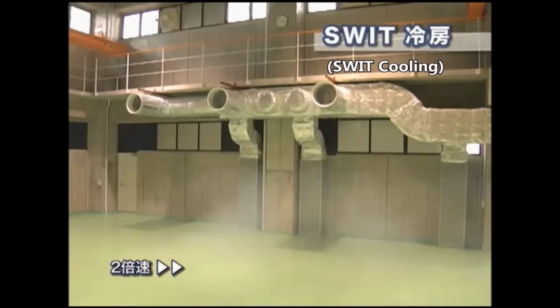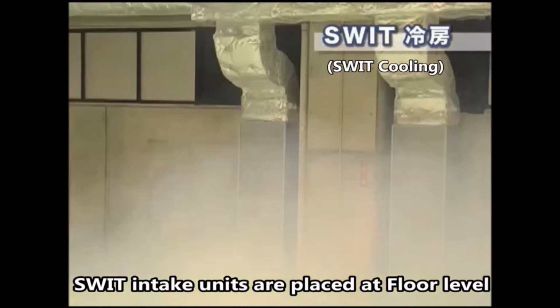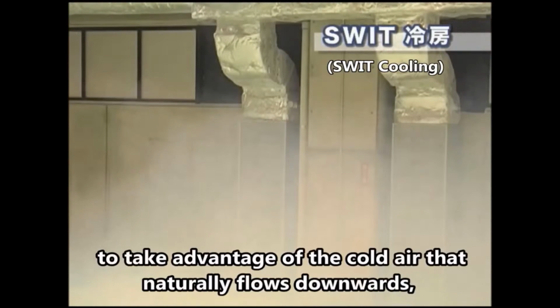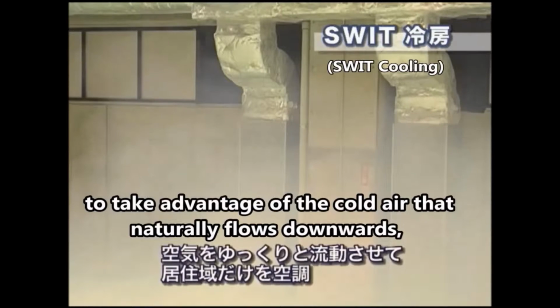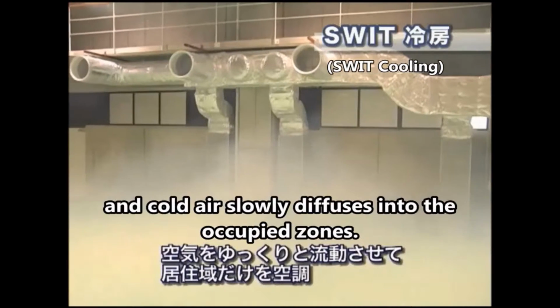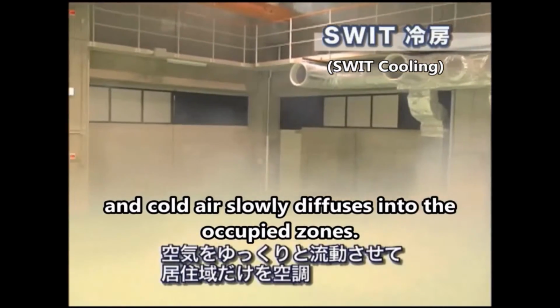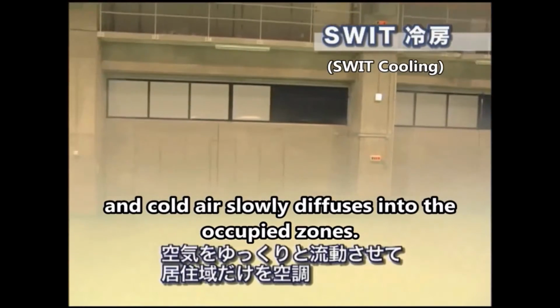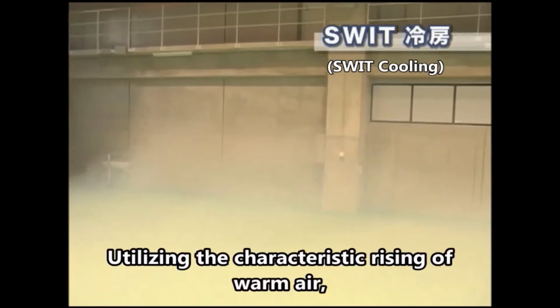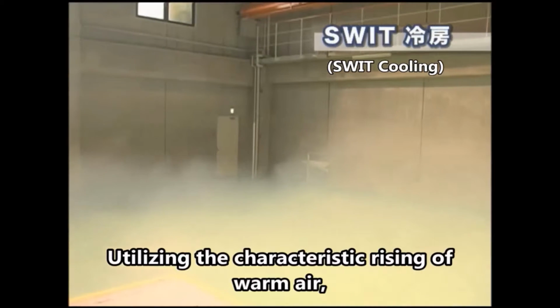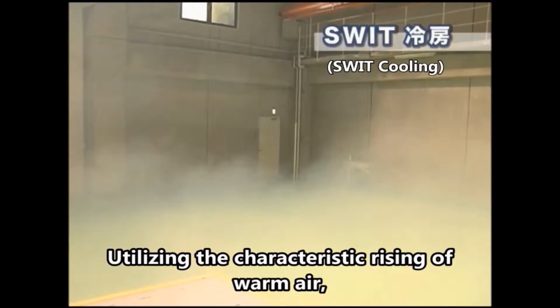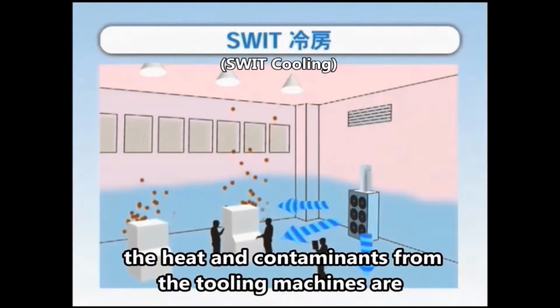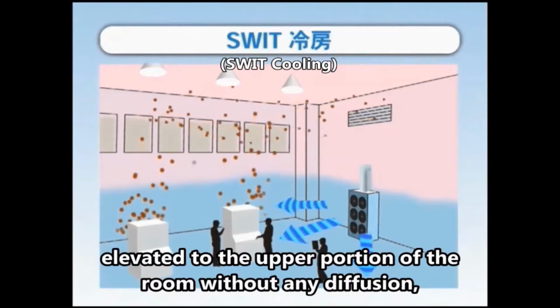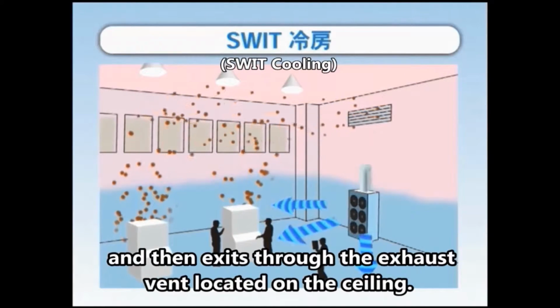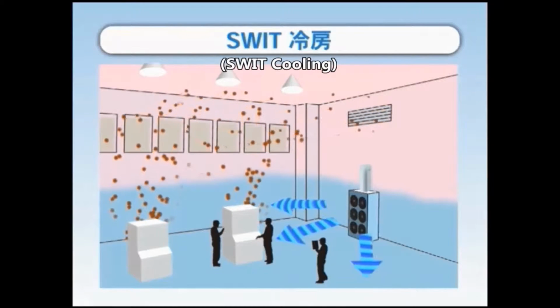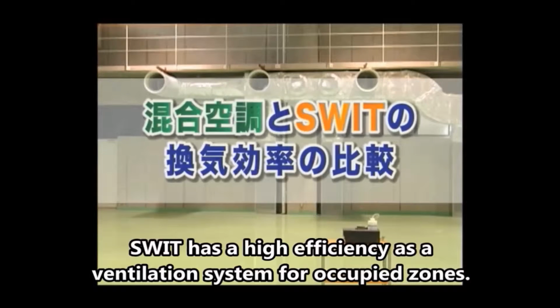Swit intake units are placed at floor level to take advantage of the cold air that naturally flows downward, and cold air slowly diffuses into the occupied zones, utilizing the characteristic rising of warm air. The heat and contaminants from the tooling machine are elevated to the upper portion of the room without any diffusion, and then exit through the exhaust vent located on the ceiling.